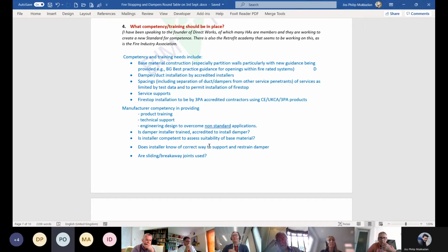And Paul, Mr. White, you're going about getting the damper manufacturers to open their eyes to walls. I think you'll always struggle to do it, because they just send it to a lab to be tested, and they go, "What do you want, a Group A, B, or C wall?" I just want a 120-minute damper. That's what they get. And you can't install it in anything because the wall thickness is too big in the test. Ian's got his hand up.